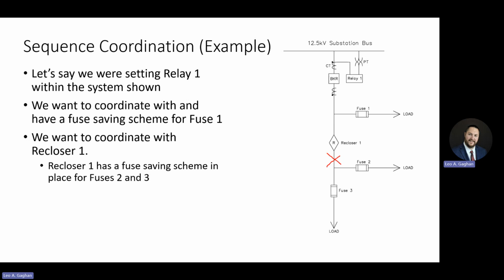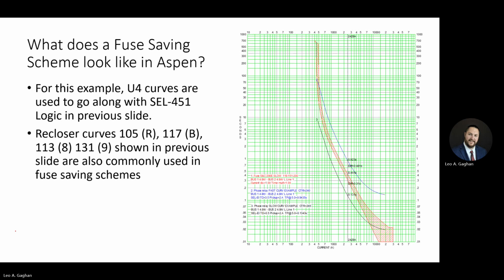So I think last time we left off on fuse saving schemes. Fuse saving scheme, as a reminder, is a fast relay curve that's intended to operate before a fuse minimum melt curve on the first trip attempt, or first shot, or say 0th shot. That's intended to save the fuse, and save a technician from going out and replacing the fuse. And then as you get further along into your reclosing sequence, you move over to that slow curve where the fault is more likely to be permanent, and that allows the fuse to isolate it, and for the relay to not trip and potentially save some customers from losing power. So that's the fuse saving scheme in a nutshell.